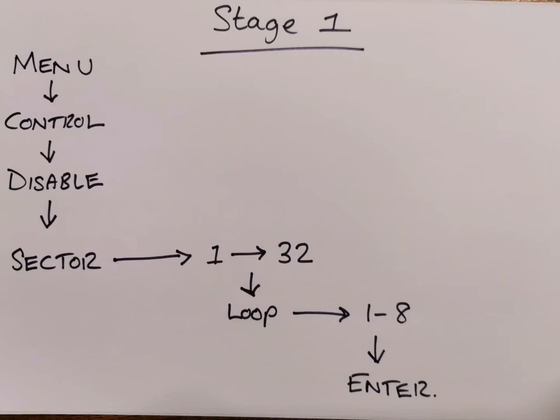If you have concluded that the panel is standalone or connected to other panels via interfaces, start by pressing the menu button, then press control or F1, then press disable or F2, then press sector or F3.